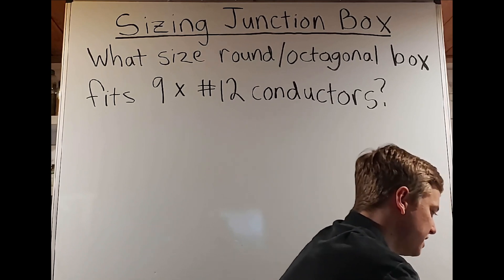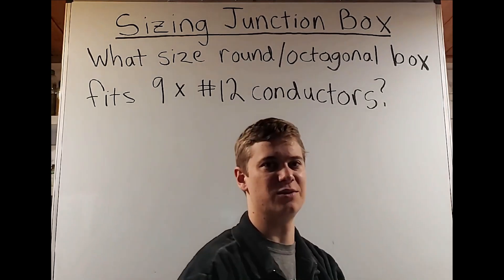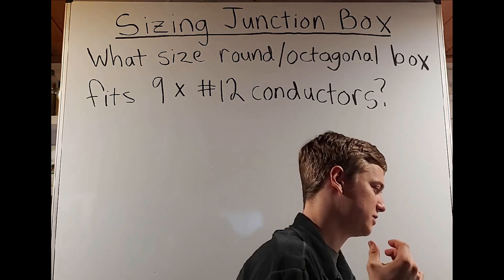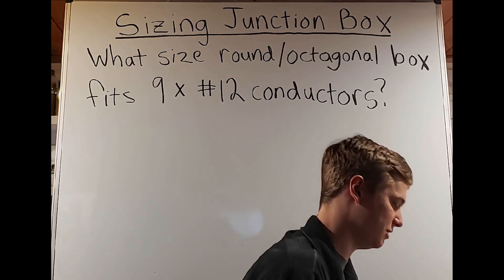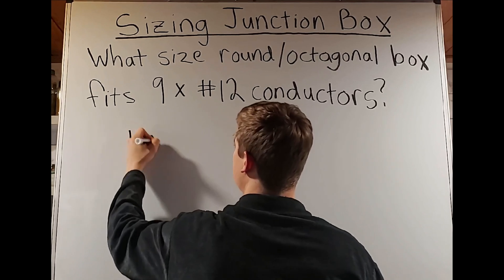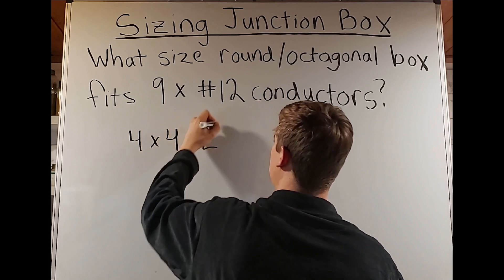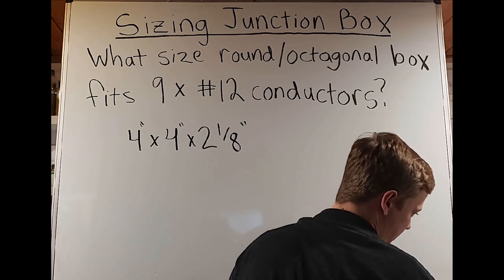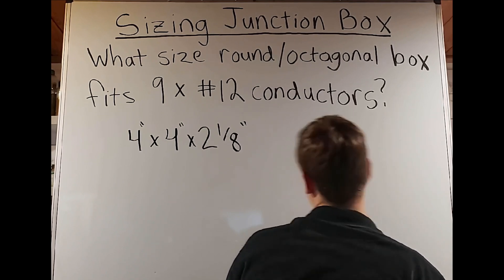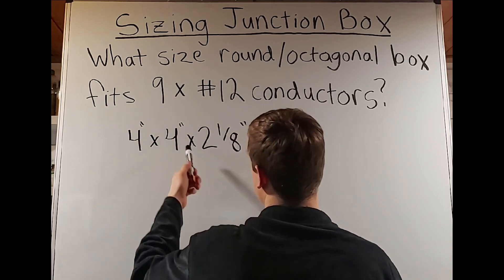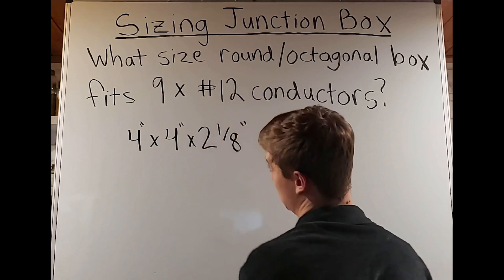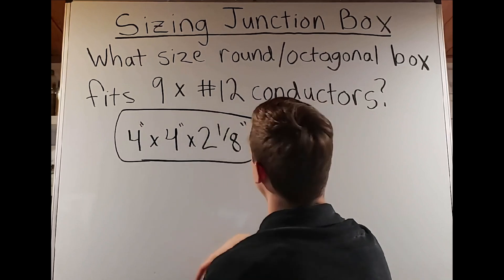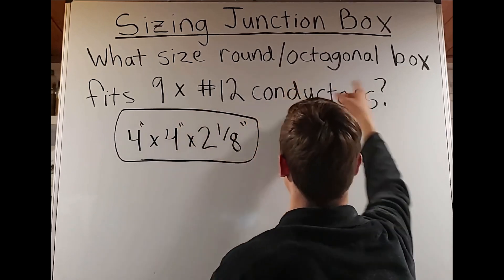Next to nine number-12 conductors for a round/octagonal box, it says four by two-and-one-eighth inches. This is giving us the volume — when only two numbers are shown, the first number is doubled to give the actual box dimensions. So this is really a four by four by two-and-one-eighth inch box. We can fit nine number-12 conductors in a four by four by two-and-one-eighth inch round/octagonal box.